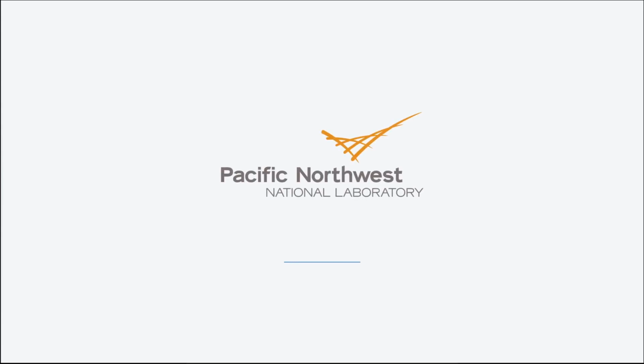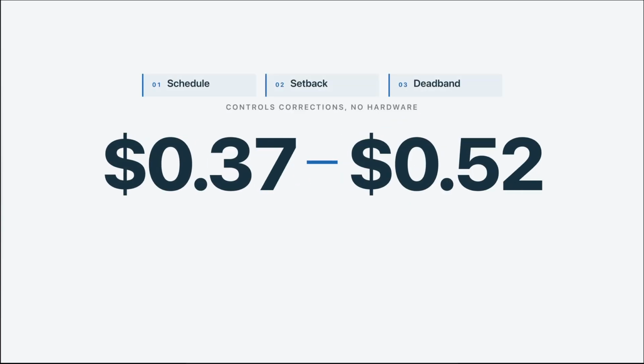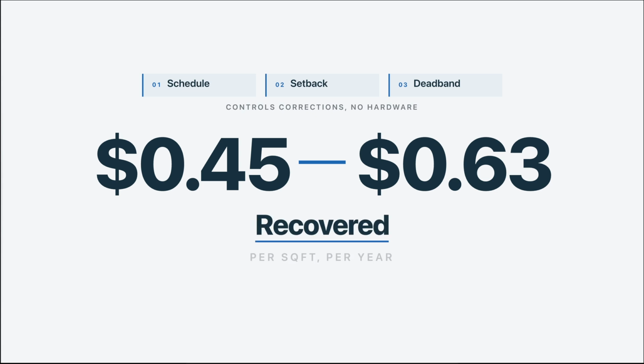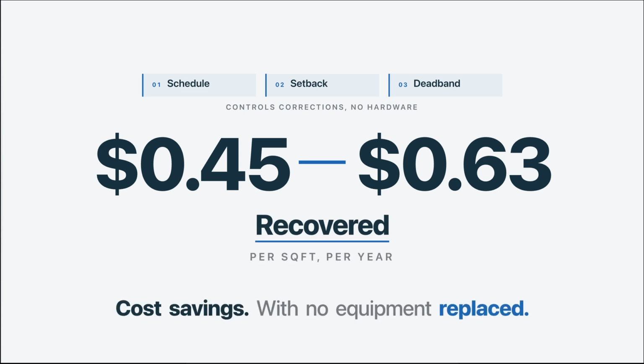These aren't obscure random findings. The Pacific Northwest National Laboratory studied them in great detail, and they consistently recover 45 to 63 cents per square foot per year. So for a 25,000 square foot building, that could be $11,000 to $15,000 in recurring annual savings without replacing equipment.